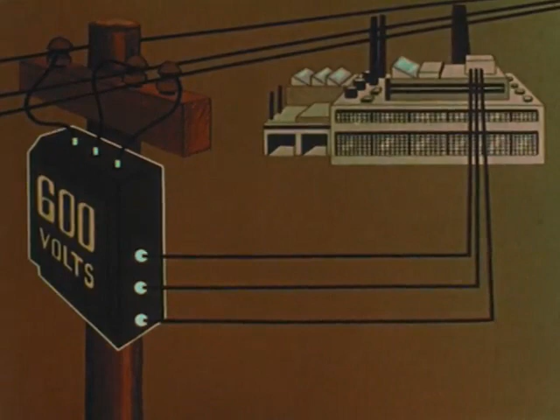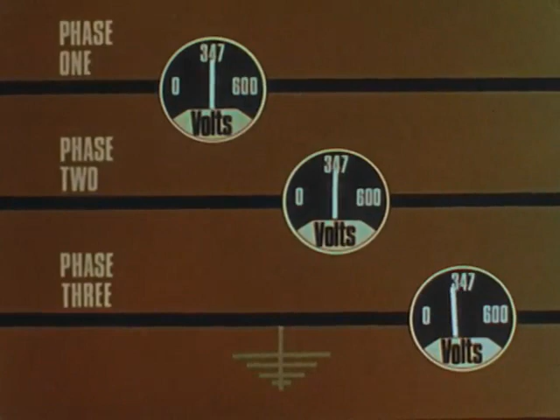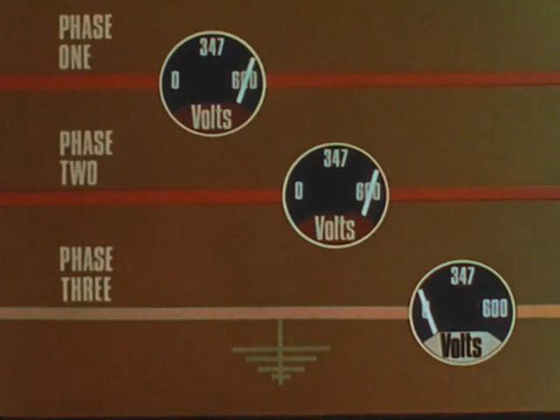But the voltage from phase to ground, due to the capacitive effect of the conductor, is about 347 volts. Should a ground fault develop in any phase, the voltage to ground on that phase will drop to 0. And the voltage on the other two phases will rise to 600 volts. Delta or three-wire 600-volt systems are usually used to operate motors and have different characteristics from star or four-wire systems used for 600-volt lighting, where a grounded neutral is necessary.